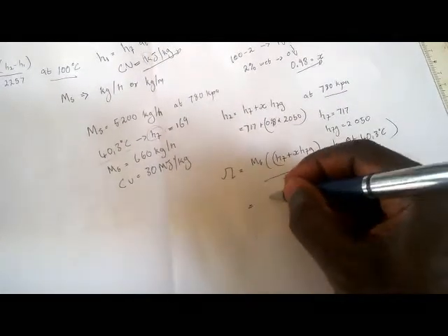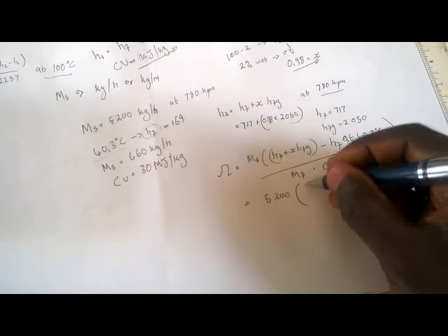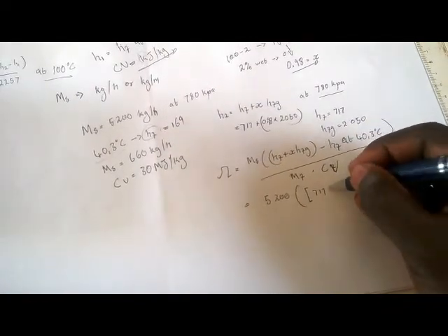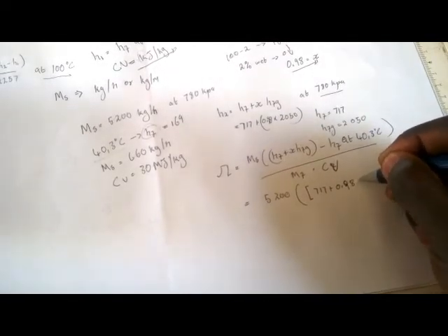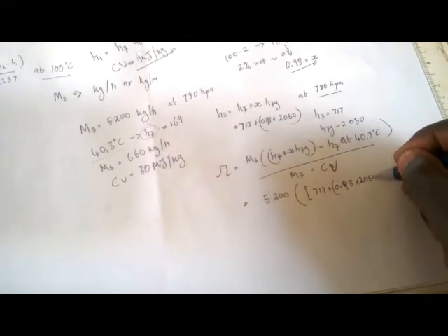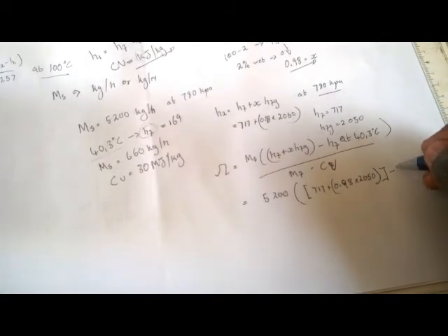Substituting: mass of steam is 5200, h2 is 717 plus 0.98 multiplied by 2050, minus h1 of 169, all divided by the mass of fuel 660 multiplied by 30 multiplied by 1000. Multiplying by 100 for efficiency gives us 67.154%. Then when calculating the equivalent evaporation, the same values are substituted using 2257 instead of the calorific heat value to find the equivalent evaporation.